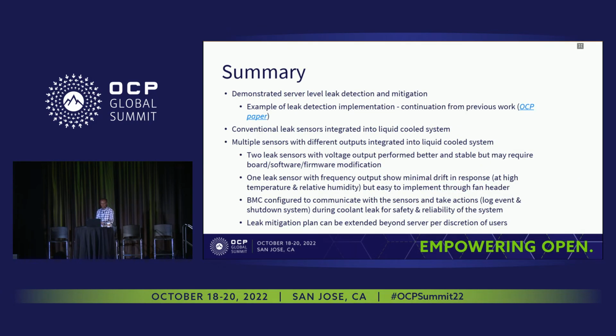All right, so as a summary, we demonstrated a leak detection and mitigation system implementation on the server level. When you scale this to rack level or maybe the entire data center level, it will all be different. So this is just the simplest and easiest way to demonstrate leak detection and mitigation implementation. Again, these are off-the-shelf sensors we can find in the market. We didn't do any kind of customization. Any customer can get these sensors from the vendors and implement them.